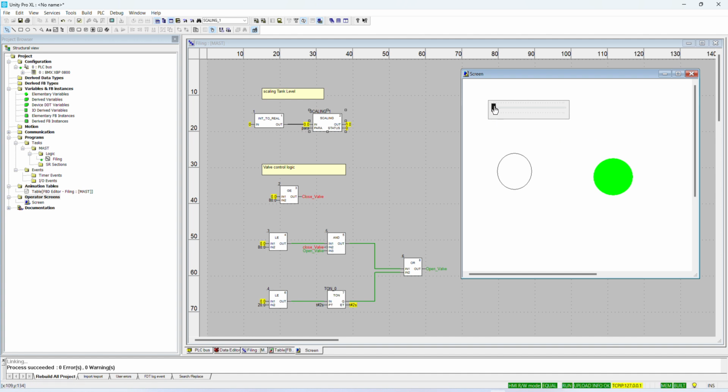Now if we go, you can see we're giving that amount, that's 8.86%, and then 25%. Our valve is still holding, if you can see there, still open. Now we go, we reach 86%, the valve is closed. You can see indicated in red, the valve is closed.